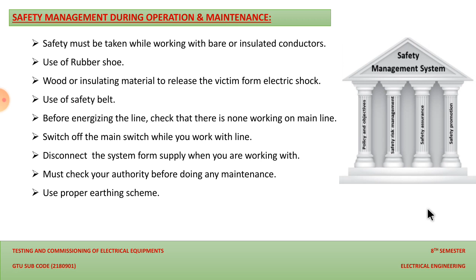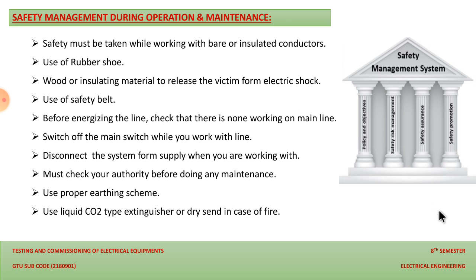Use a liquid CO2 type extinguisher or dry sand in case of fire. This is again a safety precaution we should keep in mind. Do not throw water when there is a fire, because of the risk of electric shock. So use a liquid carbon dioxide extinguisher or dry sand in case of fire. These are the safety precautions or safety management steps during operation and maintenance that we should keep in mind while working with an electrical system.